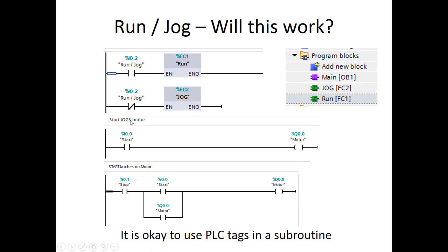In the jog subroutine, the toggle calls that and you push the start button and the motor comes on. In the run we have our holding circuit. A couple of things — we've used the output twice, which is not necessarily a good idea, but the way this is scheduled, we can only run one or the other. We put the motor into this subroutine and into this subroutine, so it's either going to run here or run here. You could get in trouble with some retentive nature of these subroutines, but it looks like this would work.